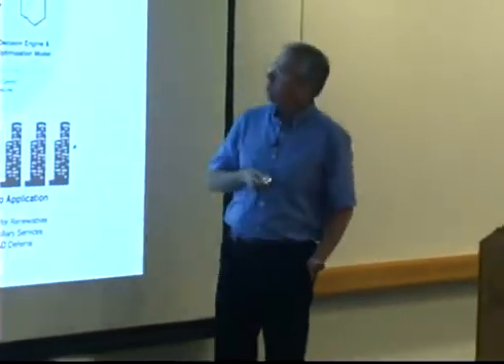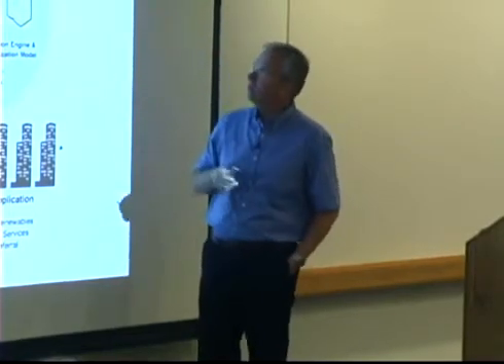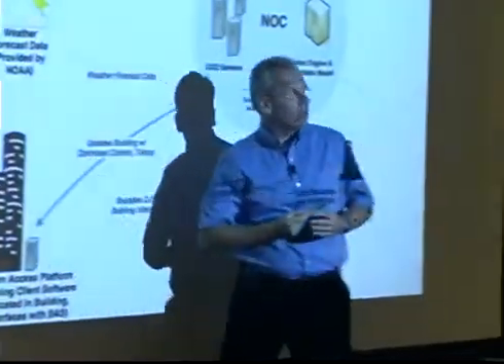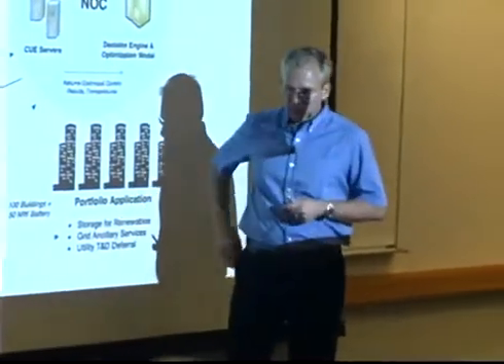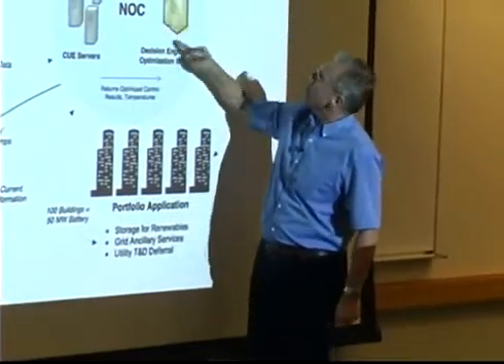And so one approach of implementing that is as a cloud-based software as a service. So here we have the cloud. Four years ago, we started to develop this, where we take weather data from NOAA, we take electric utility data from the trading desk or from the energy provider directly. We get the pricing data. We feed this into this network operating system together with the weather forecast. And we have the optimization running here. The optimal set points are sent to the building.